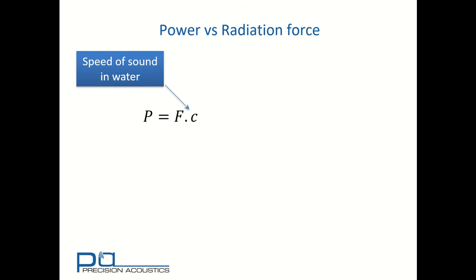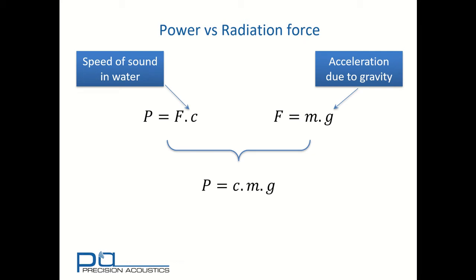We've also seen that our radiation force balance is measuring force by considering an effective mass. And therefore, from Newton's second law, we know that the acceleration of interest is the acceleration due to gravity. We can combine these two equations to give us a single expression that power is speed of sound in water times effective mass times acceleration due to gravity. This is at least true for absorbing targets. The equation is slightly different for other target types.